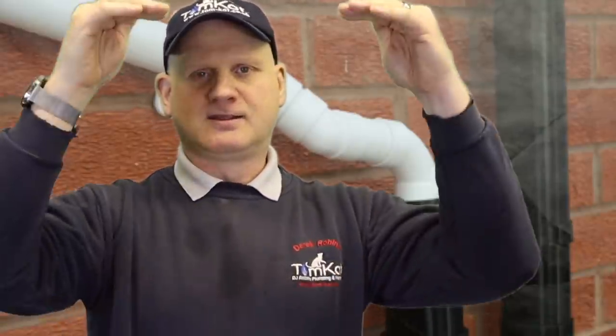Now, if we're connecting to a rainwater pipe, we definitely need to do an air break outside. And this is important because if it gets blocked up down at the bottom or it gets frozen, then you could get all that water then just going straight into the boiler. And again, I've seen a couple of boilers where they're filled up right to the top in the combustion chamber with water, where it's been connected to a downpipe or a rainwater pipe. So just be careful when you're connecting into them.